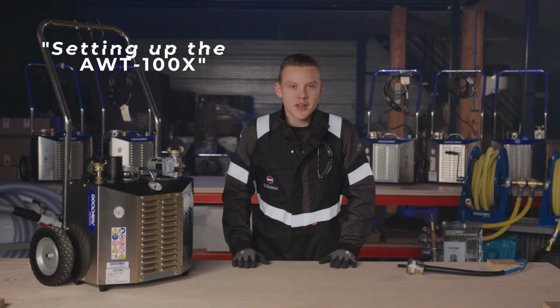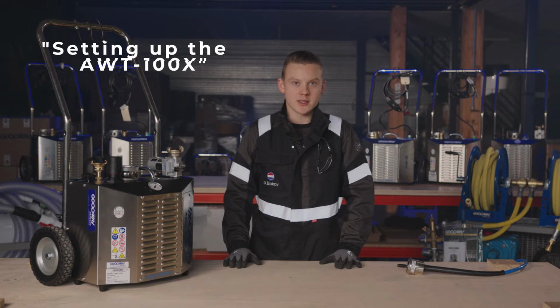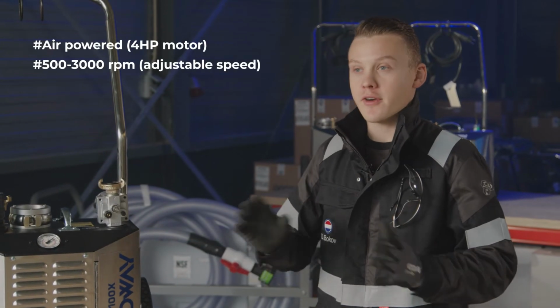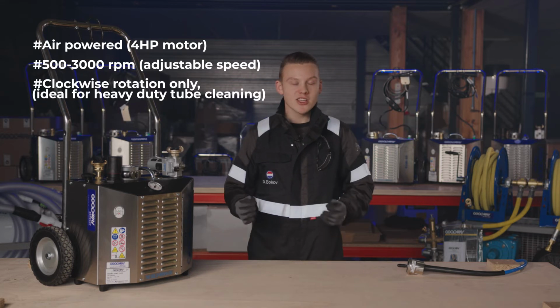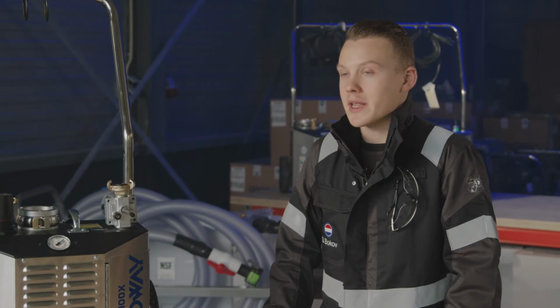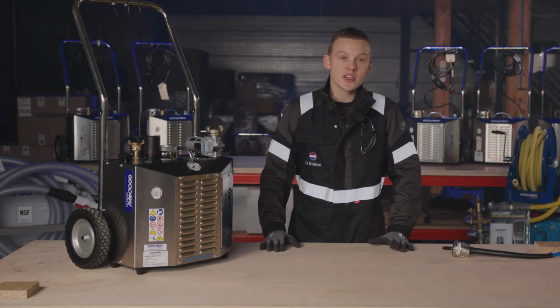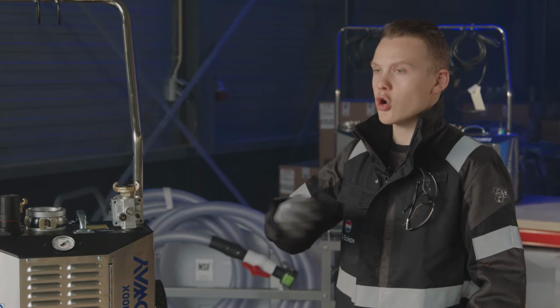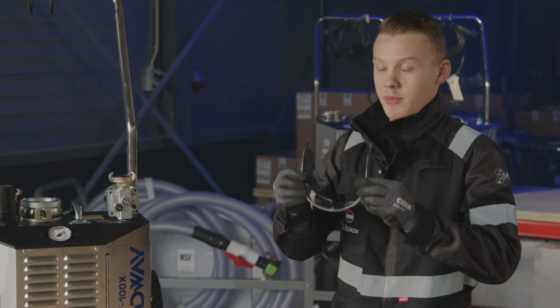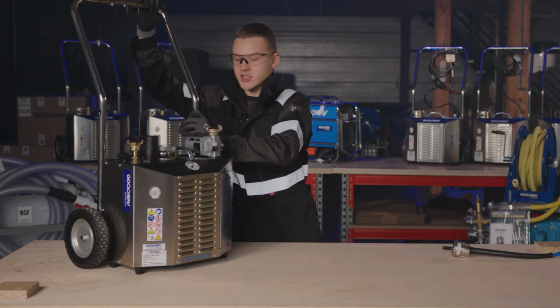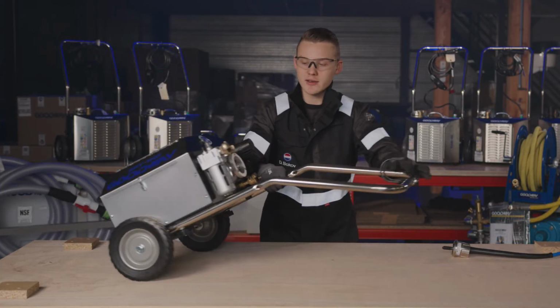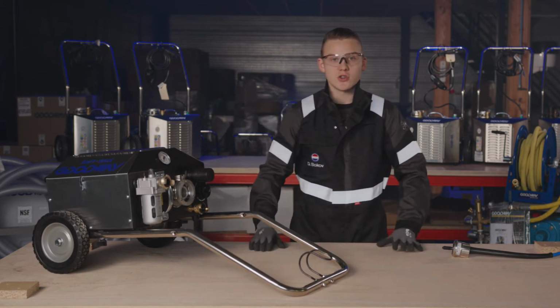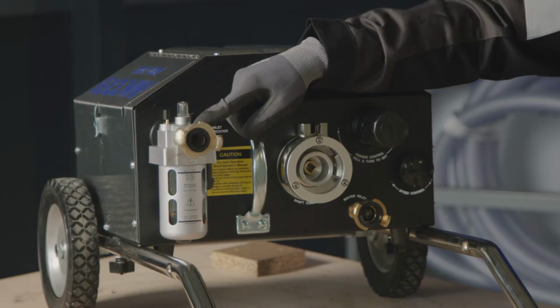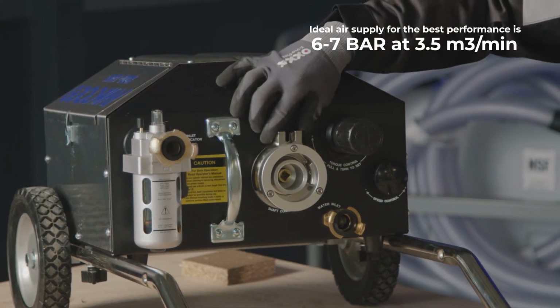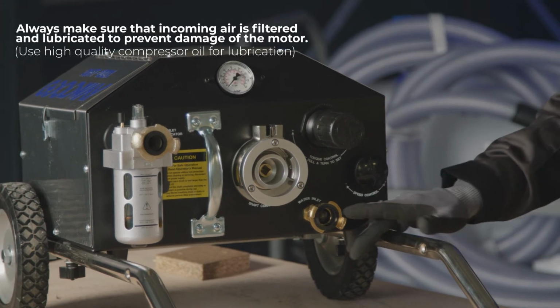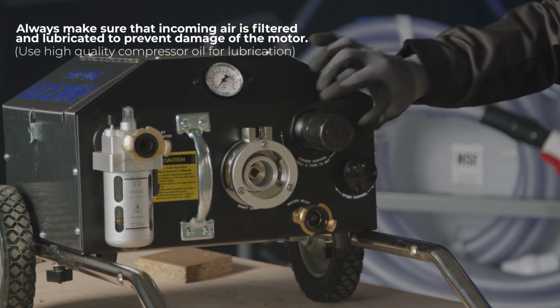The AWT 100X is Goodway's most powerful tube cleaning system. It is air-powered and can rotate from 500 to 3000 RPM. This is especially useful for tough industrial tube cleaning applications. Some examples can be heat exchanger or reactor tubes. As always, when setting up your tube cleaning system, make sure to wear the proper PPE. Since the AWT 100X is used with a dolly, it is important to use it in a horizontal situation. Here you have your air intake with lubrication, shaft manifold for connecting a flexible shaft, water supply, speed control and torque control.